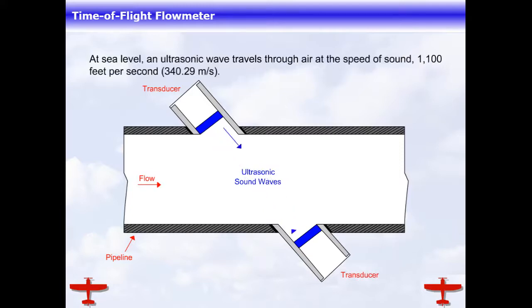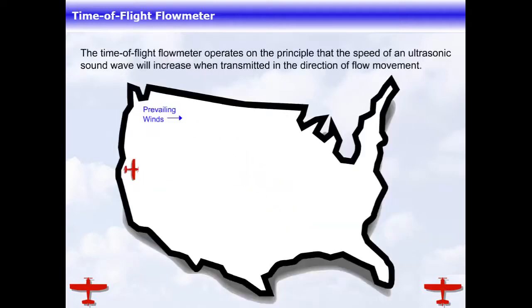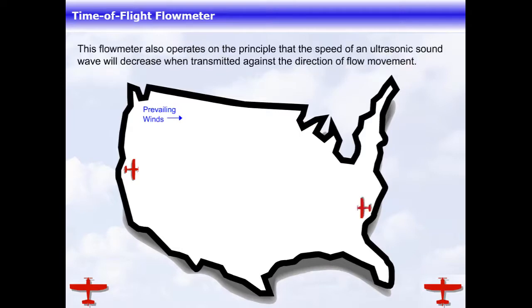At sea level, an ultrasonic wave travels through air at the speed of sound, 1,100 feet per second, or 340.29 meters per second. The time of flight flowmeter operates on the principle that the speed of an ultrasonic sound wave will increase when transmitted in the direction of flow movement. This flowmeter also operates on the principle that the speed of an ultrasonic sound wave will decrease when transmitted against the direction of flow movement.